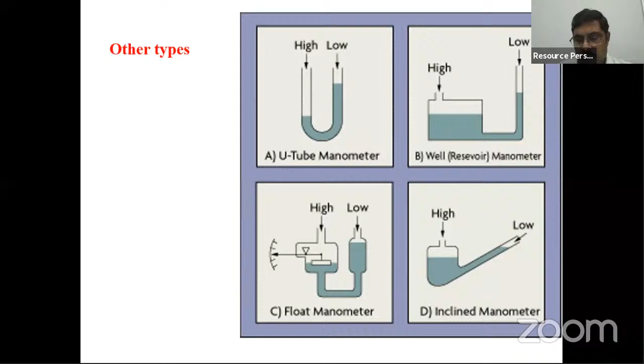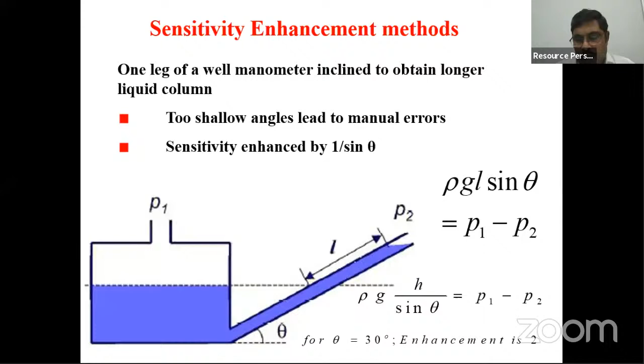What I want to tell you is, suppose if you choose mercury, the pressure range is - say if you want to measure the pressure delta P above 500 kilopascal or maybe 100 kilopascal, you can go for mercury. If the pressure delta P is less than 100 kilopascal, you can go for water, or if it's less than 50 kilopascal or in the range of pascal, then you can go for the inclined type manometer. So selection of the manometric fluid purely depends on your operating range - you should not go blindly with this.